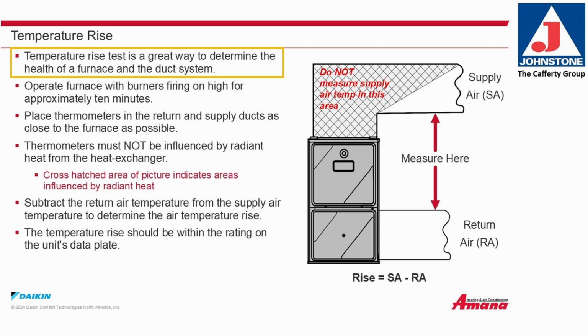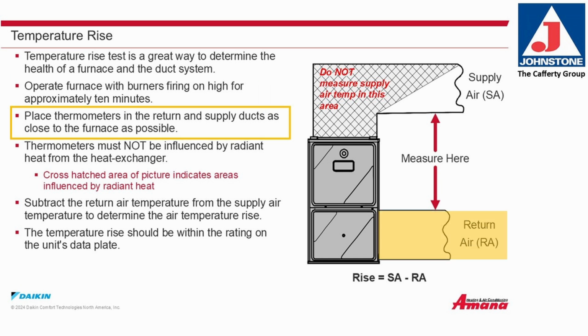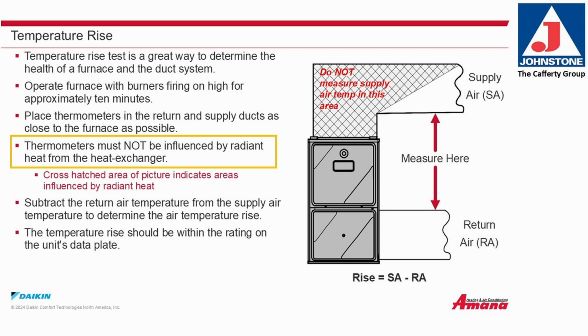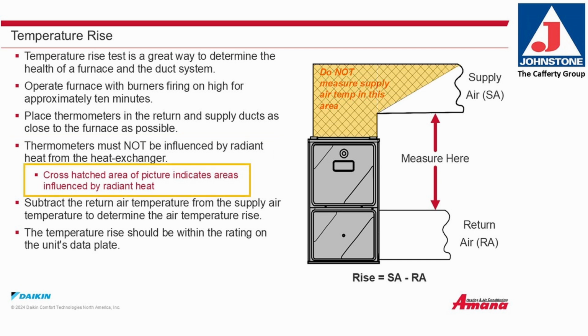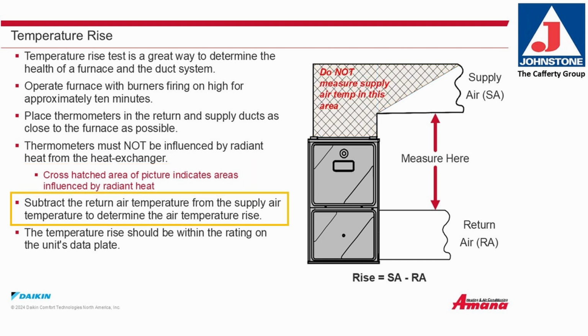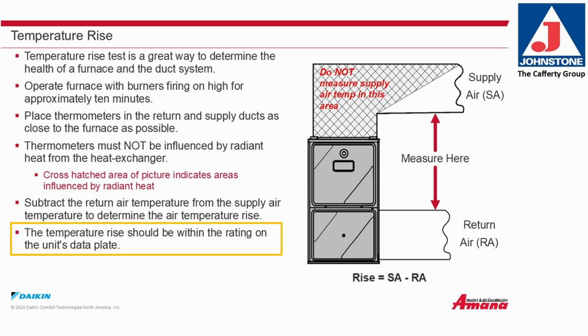Operate the furnace with burners firing on high for approximately 10 minutes. Place thermometers in the return and supply air ducts as close to the furnace as possible. Thermometers must not be influenced by radiant heat from the heat exchanger. The cross-hatched area of the picture indicates areas influenced by radiant heat. Subtract the return air temperature from the supply air temperature to determine the air temperature rise. The temperature rise should be within the rating on the unit's data plate.